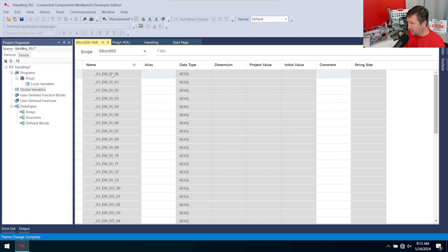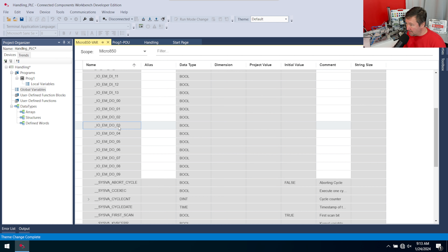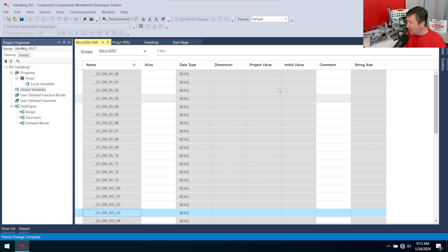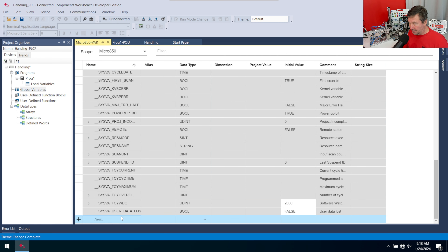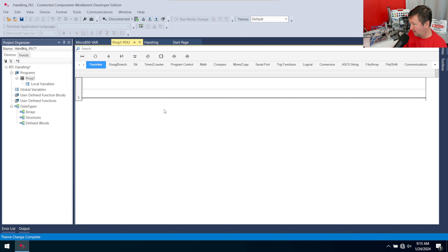One difference between Studio 5000 and the micro 800 is that in Studio 5000, our address would be something like Local:1:I.Data, and we could simply copy that to a double integer and read it to another PLC. In the micro 800, we don't have this at the word level, so we need to get all of these into an integer to read across the network. We'll add 'inputs from main PLC' as a double integer and 'outputs from main PLC' also as a double integer in our global variables.